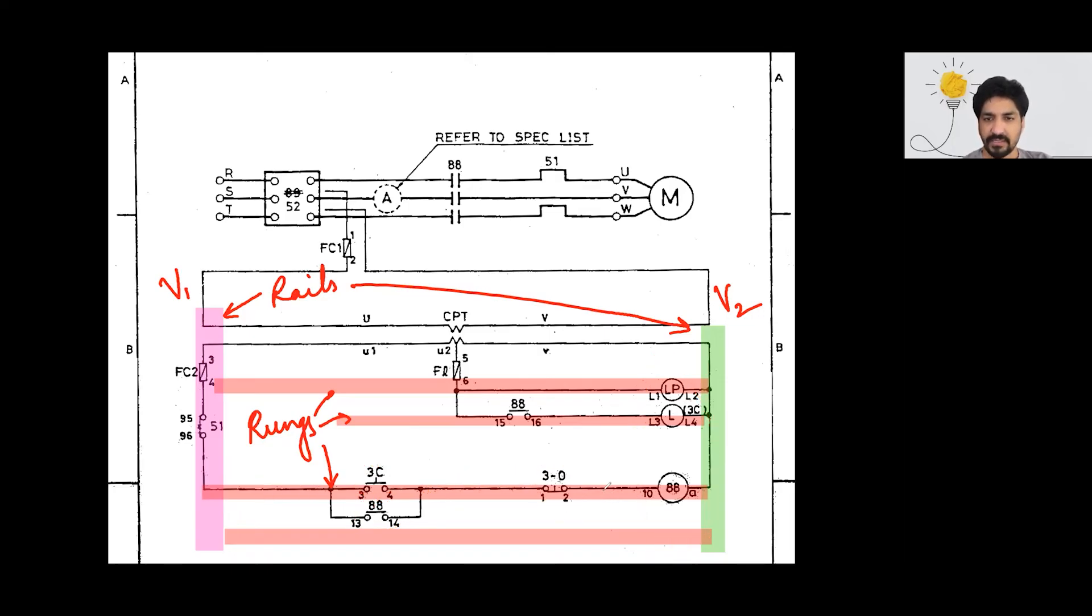If we see the switches, there is no end to the number of switches you can put. You can put 10 switches in series, it doesn't matter. Because switches are nothing but either a straight line or an open circuit. So it is not a load at all. That's why you can put multiple in the same line or in series. And there is no fixed location, you can put them anywhere you feel like. Only thing is you need to be careful where you are putting the loads. So that's how we draw the circuit: a power circuit on the top, then remaining is control. Control is looking like a ladder logic with rails having different potential, and then rungs.